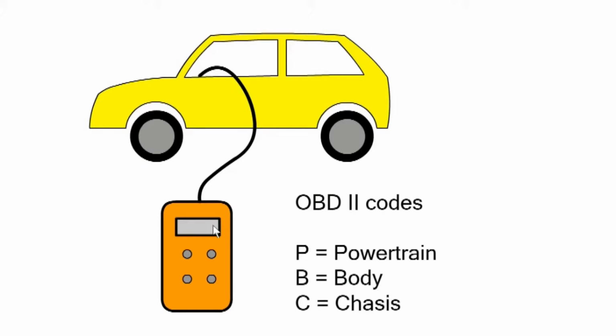Caution must be exercised when using a fault scanner, as quite often when there is a faulty reading from a sensor, the source of the problem might be elsewhere in the system. Also, high resistance electrical cable connections can lead to erroneous readings, so check everything, and as a last resort, change the sensor.